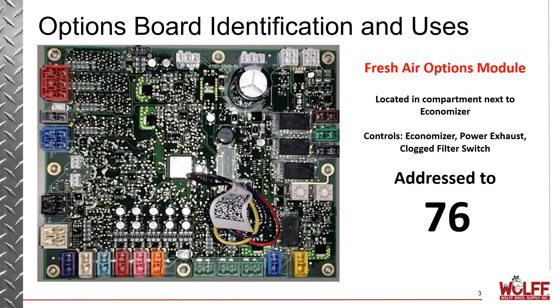This is the fresh air options module. You're going to find this located in the compartment next to the economizer. It controls options like the economizer, the power exhaust, and the clog filter switch. This board needs to be addressed to 76.